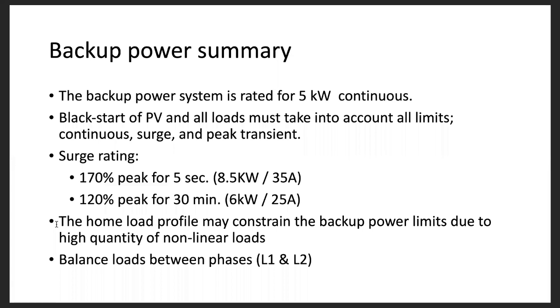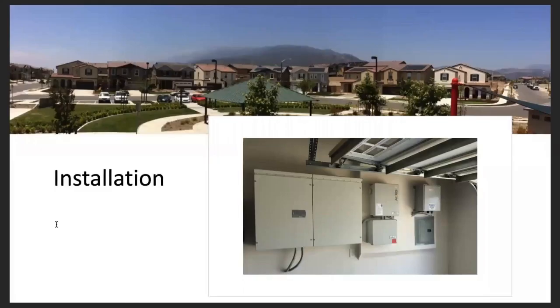So say, for example, you've got a refrigerator that might operate at 200 watts, but surges up to 1800 watts when that compressor kicks in, and you've measured it. And you've got a microwave that operates at 1000 watts maximum that might cycle on and off. You want to make sure that you put that microwave on line 2 if the refrigerator's on line 1, because you want to make sure that you don't exceed the max current on the inrush side of things. You obviously want to balance the loads, especially for nonlinear loads. So that's the planning stages. That's the first big step in success with the battery products.